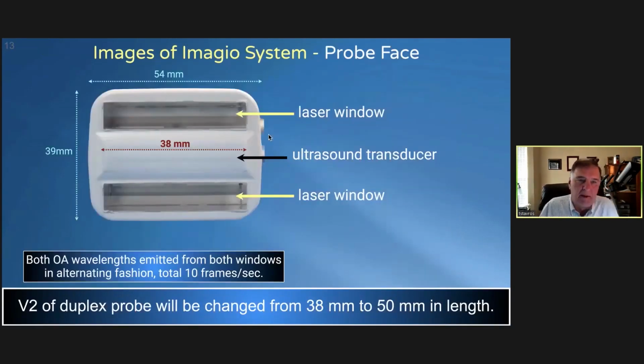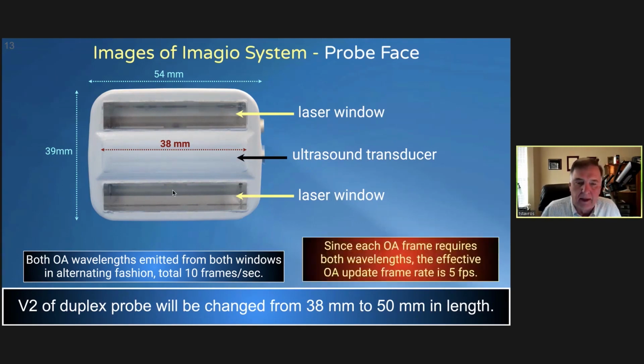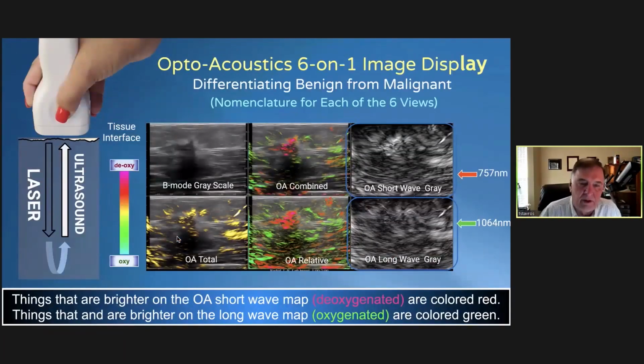This is an image of the face magnified. It's a 38 millimeter transducer. Gen 2 will be a 50 millimeter transducer. It's important to know that both wavelengths are fired out of both windows. It's not like one wavelength is fired out of one window and the other wavelength fired out of the other. The 50 millimeter transducer will be an improvement because in breast imaging, we prefer to use a longer transducer if we can. This is how the display is.